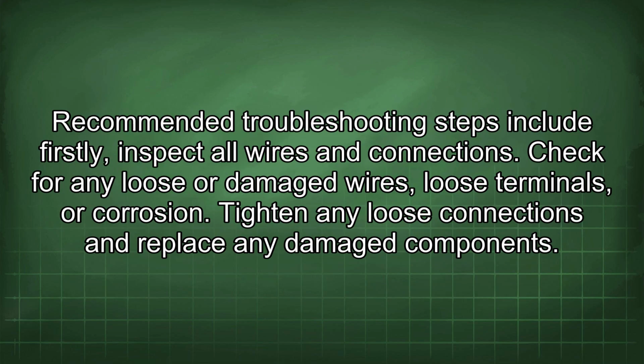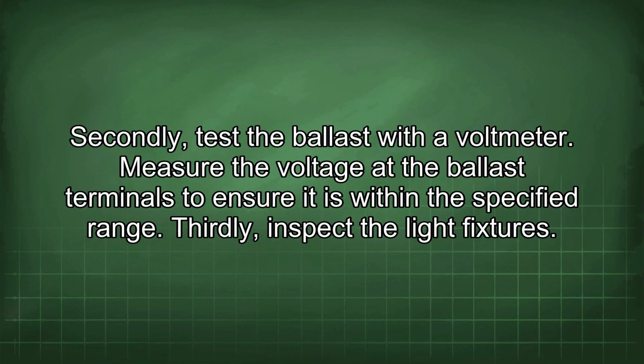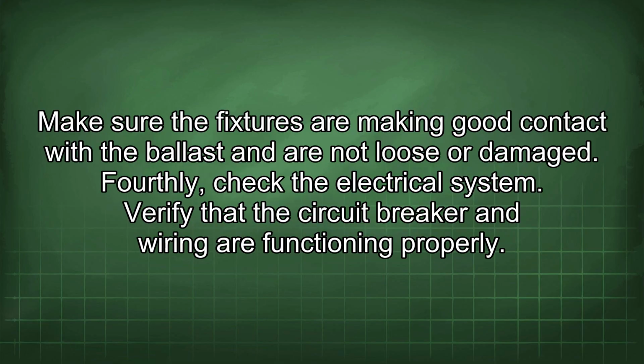Recommended troubleshooting steps include: firstly, inspect all wires and connections. Check for any loose or damaged wires, loose terminals, or corrosion. Tighten any loose connections and replace any damaged components. Secondly, test the ballast with the voltmeter. Measure the voltage at the ballast terminals to ensure it is within the specified range. Thirdly, inspect the light fixtures. Make sure the fixtures are making good contact with the ballast and are not loose or damaged.